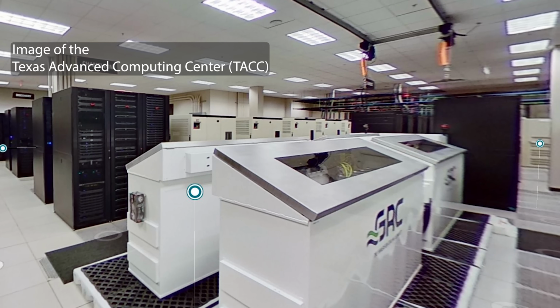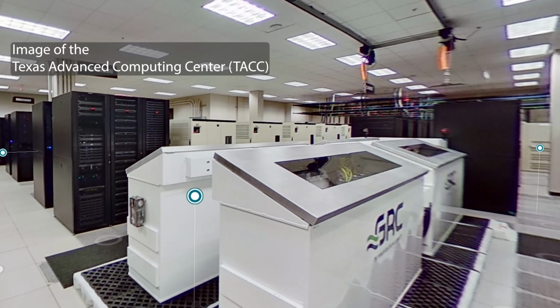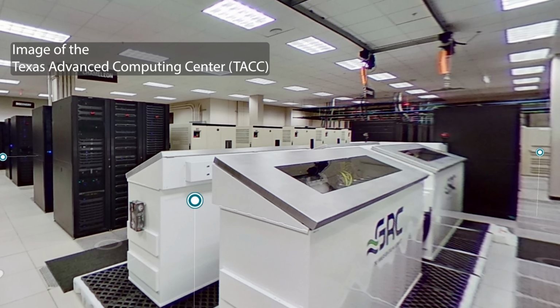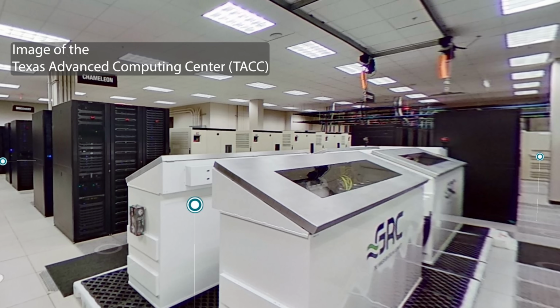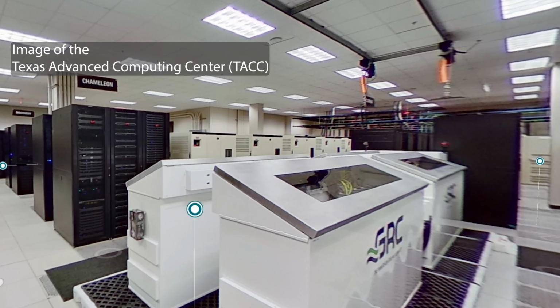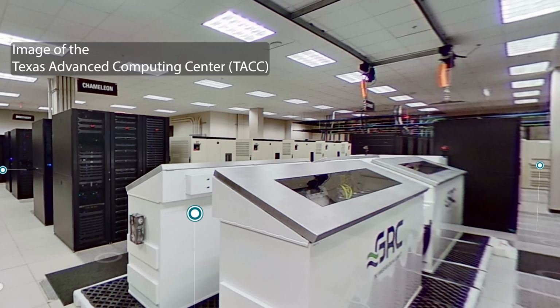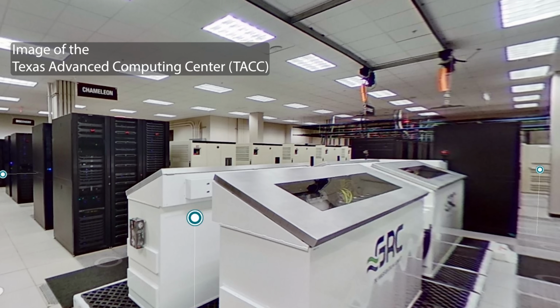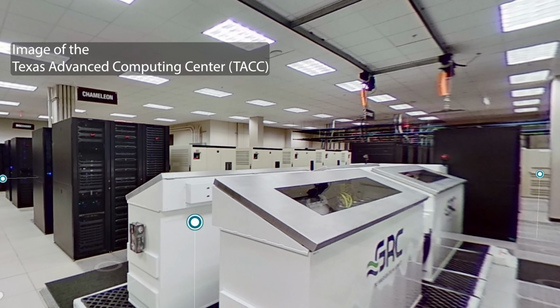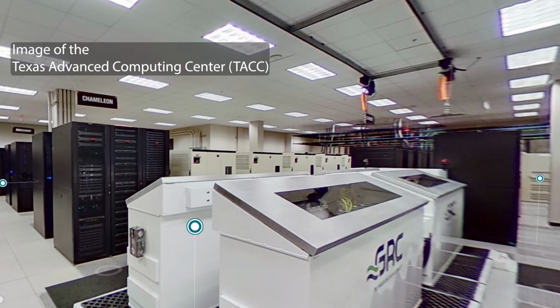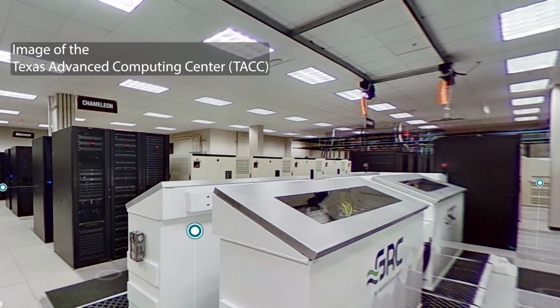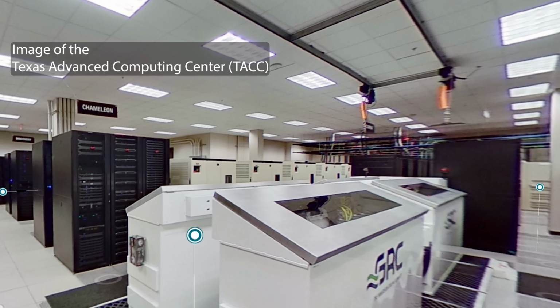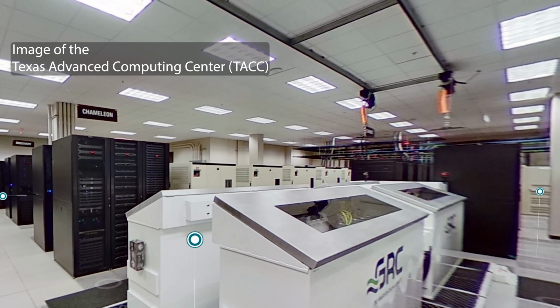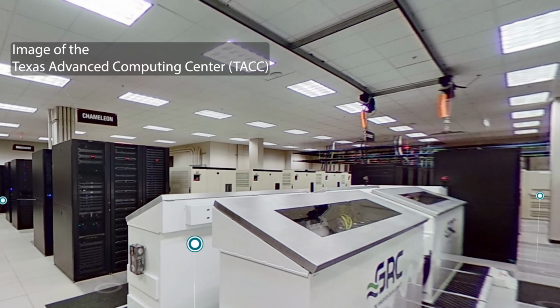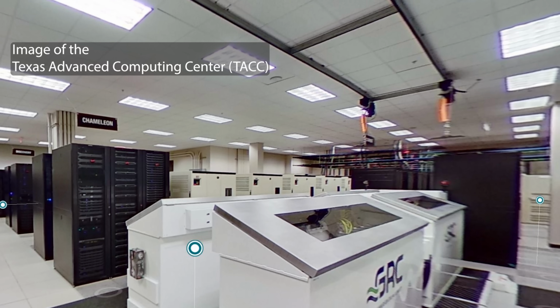So what you see is that not only do you have to have a different footprint just because the racks are horizontal versus vertical, but you also have to have things like hoists on the ceiling to be able to lift the servers out of the tub of fluid or just drop them in there, because a lot of servers are still pretty heavy and you have to lift them up sometimes a couple feet, or meter or whatever, to get them out of these tanks. And so you actually have to have hoists on the ceiling to be able to get them out of immersion tanks and service them.